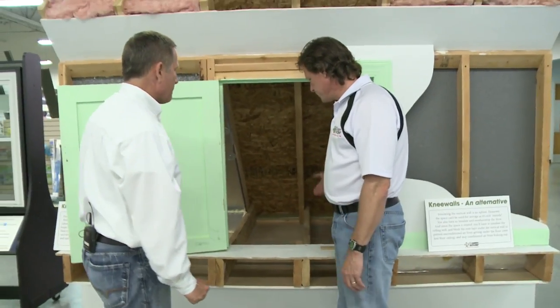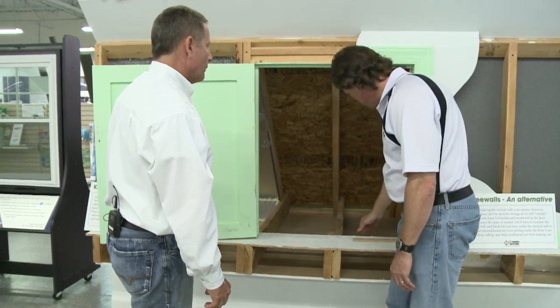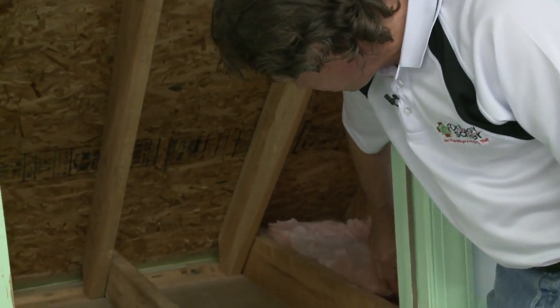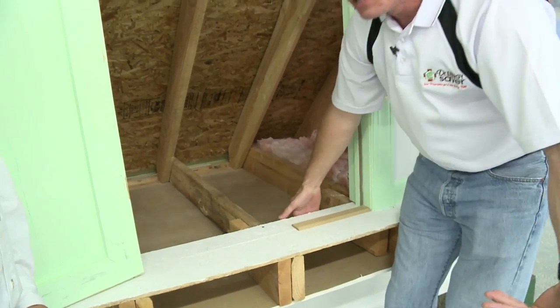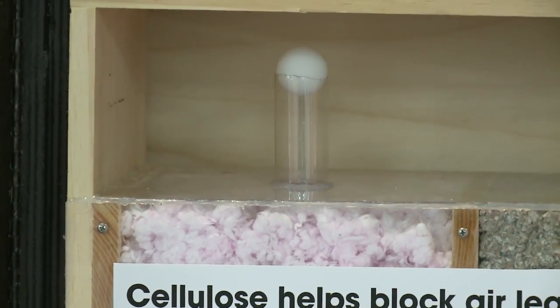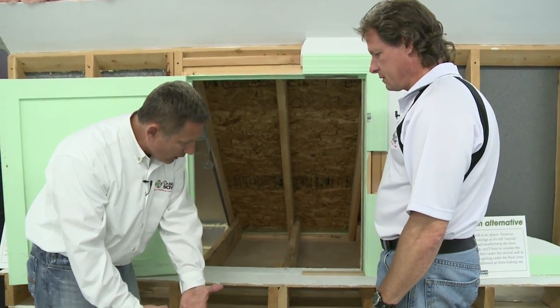So the space is vented. We have cold air coming in the wintertime. And then the builder may have put some fiberglass insulation on the floor here. But of course, it's open — it's an open structure and the air can get through this fiberglass. That cold air can go right through, making cold ceilings downstairs and cold floors upstairs. We've already shown that air travels through fiberglass insulation, so that cold air makes its way right through.